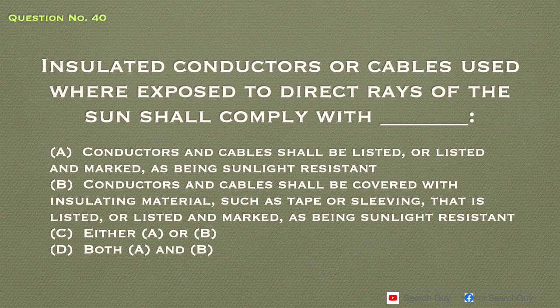Question number 40. Insulated conductors or cables used, where exposed to direct rays of the sun, shall comply with blank. A. Conductors and cables shall be listed, or listed and marked, as being sunlight resistant. B. Conductors and cables shall be covered with insulating material, such as tape or sleeving, that is listed, or listed and marked, as being sunlight resistant. C. Either A or B. D. Both A and B. Answer: C. Either A or B.